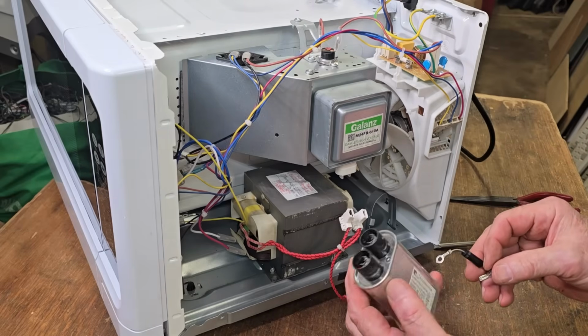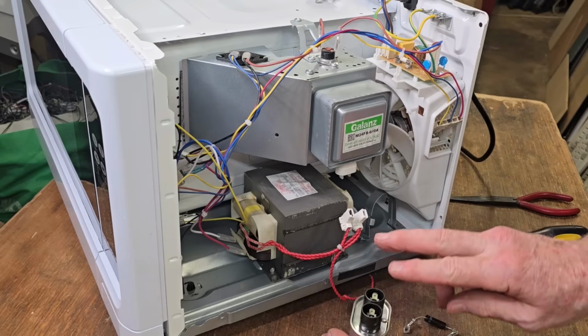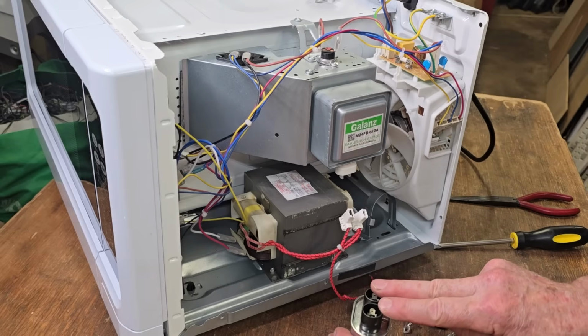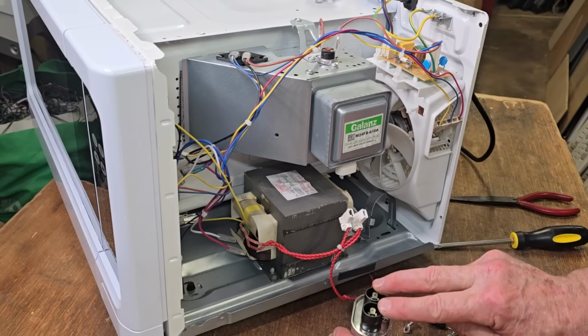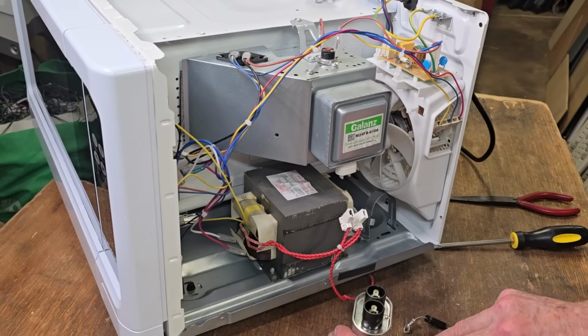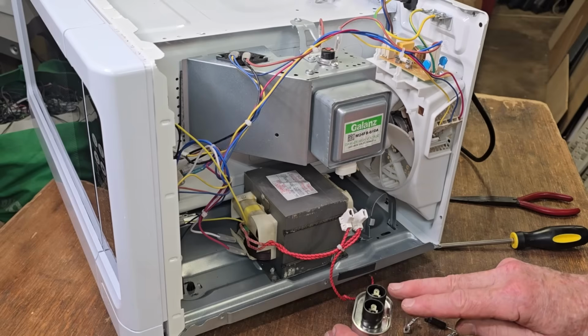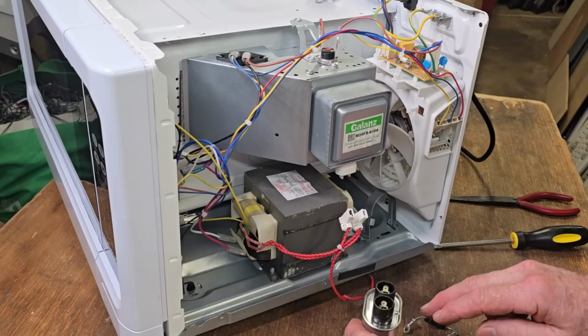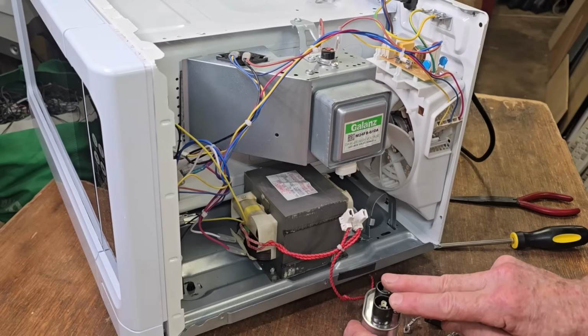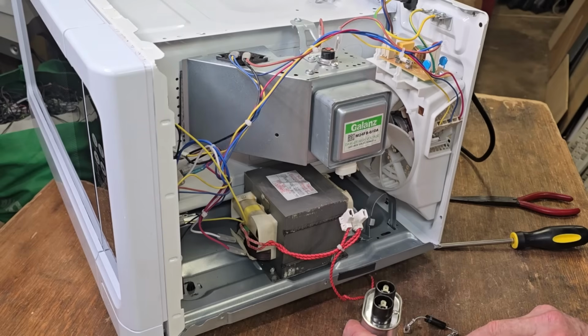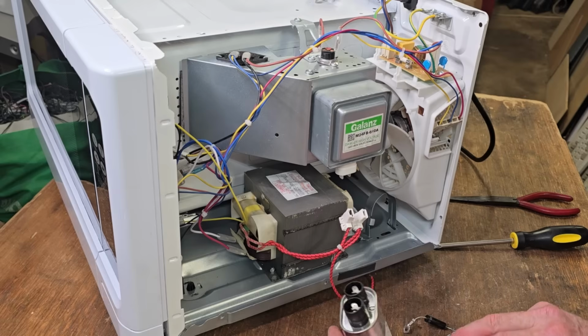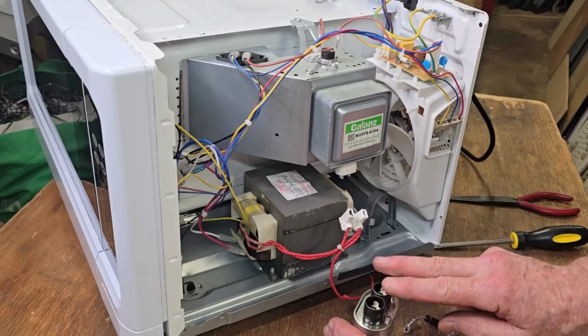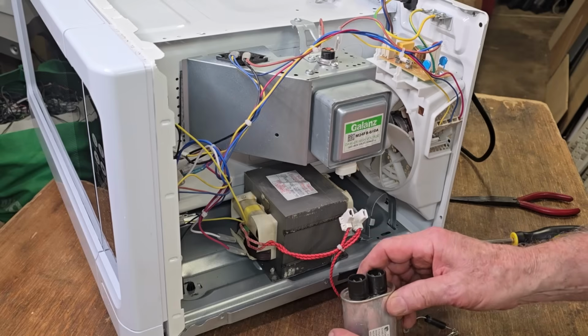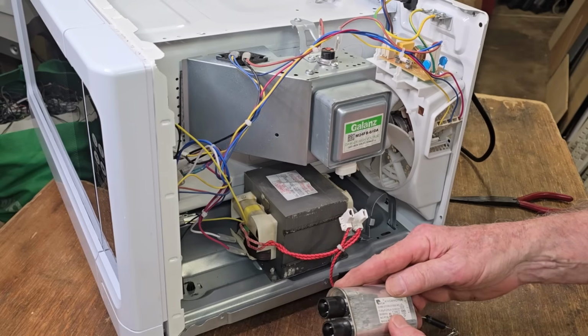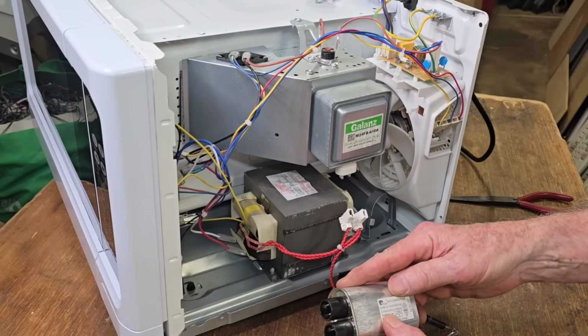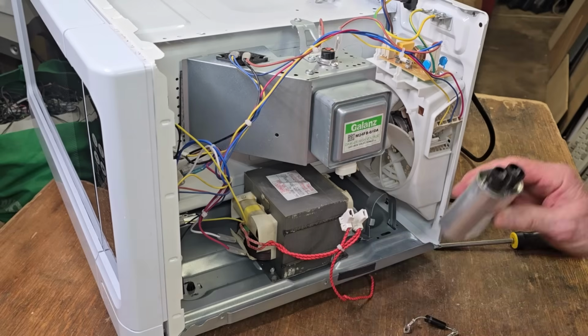The capacitor should be pretty easy to check - we can do a continuity test straight across. There should be no continuity between the terminals or with the case. I believe they can short, so that would show up. You'd want to make sure they're discharged before you pull them out anyway, but you certainly don't want to put your meter on there while it's got a lot of voltage - trying to do a continuity test that way, you'll end up blowing your meter up. Easy enough though, if it reads open circuit, which it should, to do a capacitance test on it. This one is supposed to be 1.05 microfarads, so we'll check that in a minute.